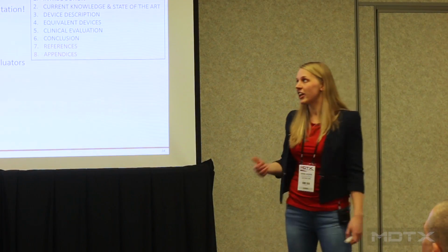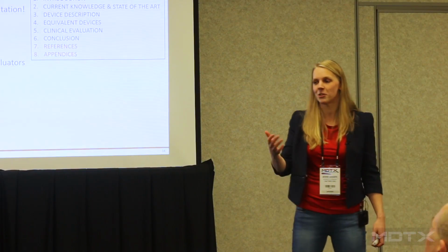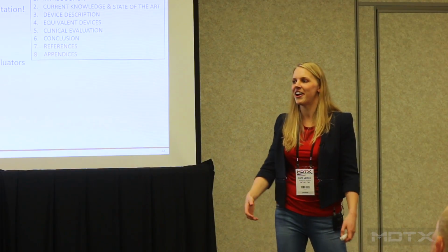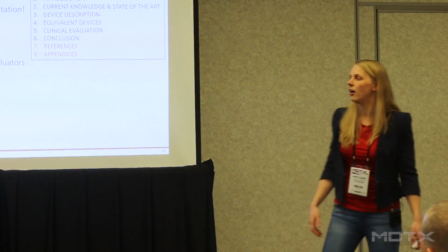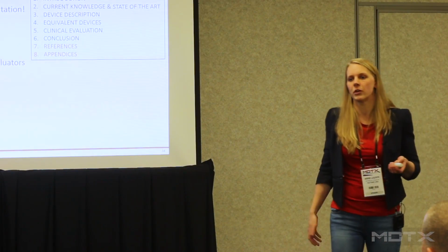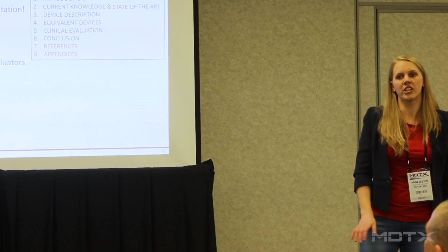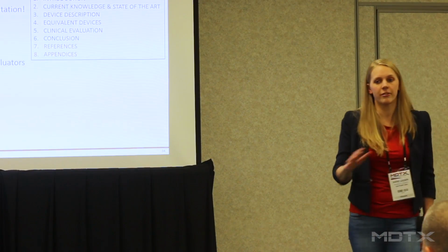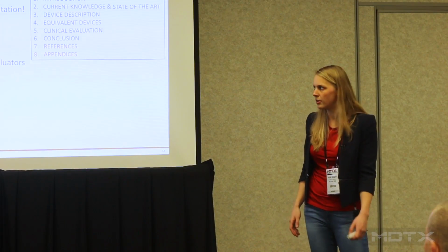Make sure you have a qualification and a declaration of interest for all the evaluators, because as I mentioned before, you have to justify your team of evaluators, but you also have to show whether or not they have interest in the outcomes of the report. And provide full text copies of all the literature that you use, for the state-of-the-art part, but also for the device part, or any sections in between where you use literature.